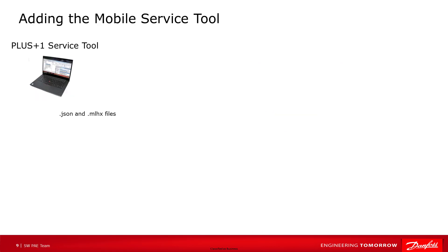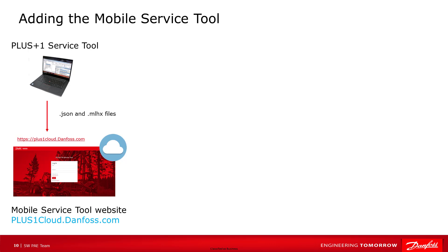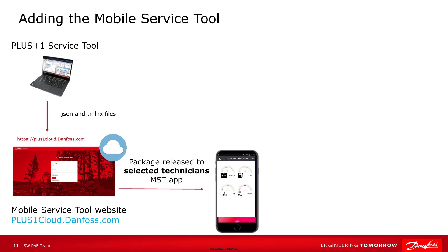I'll go over what the high-level view to develop, administer, and release a mobile service tool package looks like, and do a demo of the app on a mobile device. The desktop service tool is used to create the files that get uploaded to the Plus One Cloud website where the developer creates the service screens, creating gauges, and read and write parameters based on the signals designed in the GUIDE application — very similar to building a service screen in the desktop service tool. The firmware can also be loaded into the Plus One Cloud website to update machines. The administrator manages the releases and decides which technicians get those releases, allowing version control — unpublishing old releases and sending new releases to technicians that need them.